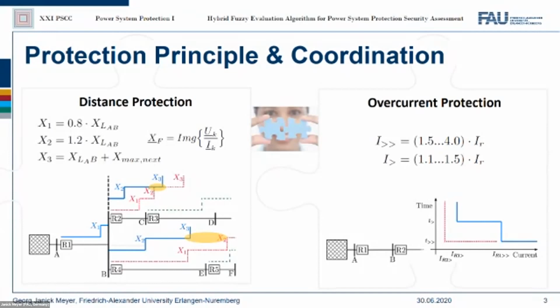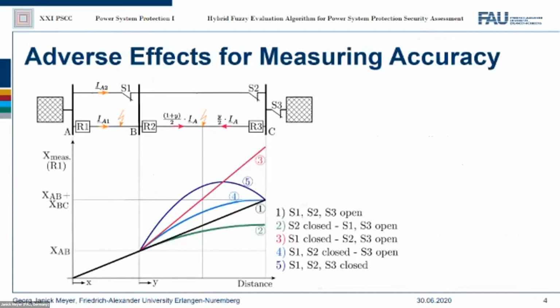But let us take a closer look at reality with a little example I've got on the next slide. Especially in the practical use of distance relays, a number of influencing factors that adulterate the measurement result must be taken into account. In this figure, a simple grid model is shown. If all three switches S1, S2, and S3 are open, we actually have just a stub line fed by the connected source on the left side.